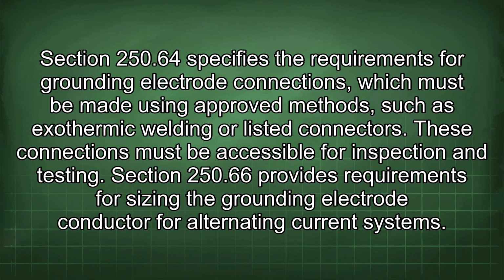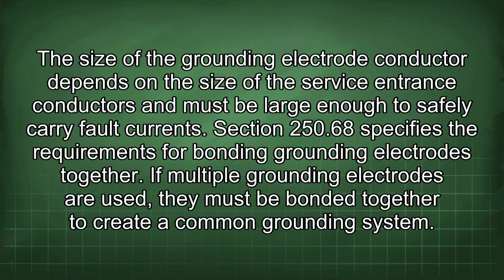Section 250.66 provides requirements for sizing the grounding electrode conductor for alternating current systems. The size of the grounding electrode conductor depends on the size of the service entrance conductors and must be large enough to safely carry fault currents.